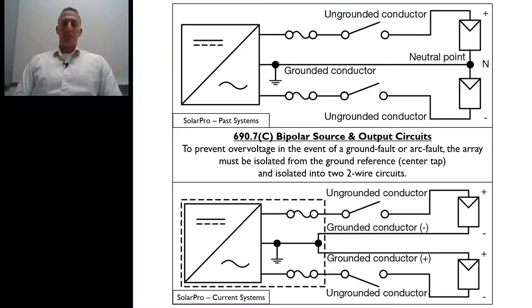In 690.7C of the 2017 National Electrical Code, it talks about bipolar source and output circuits. And so what it states, it says to prevent overvoltage in the event of a ground fault or arc fault, the array must be isolated from the ground reference or that center tap and isolated into two two-wire circuits.